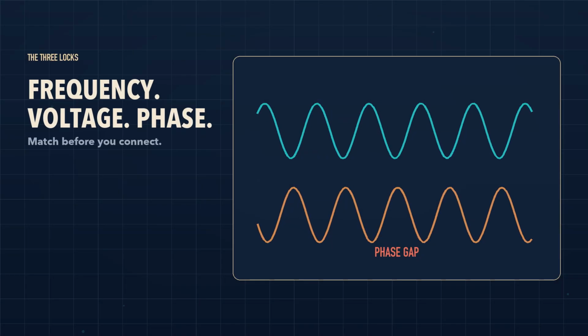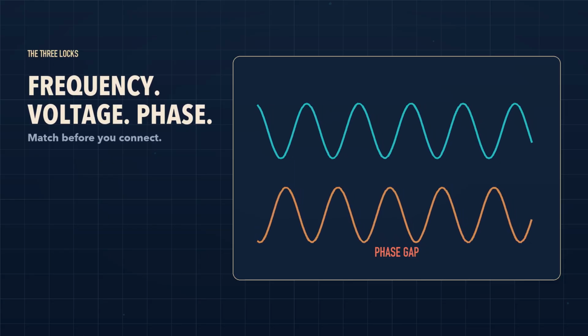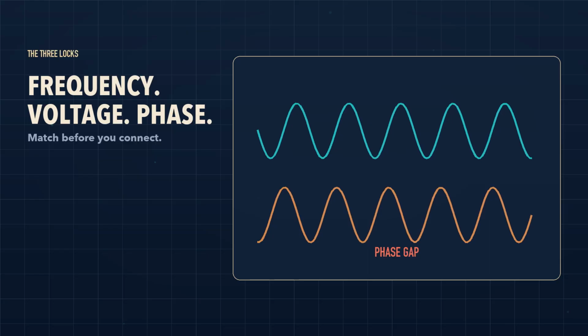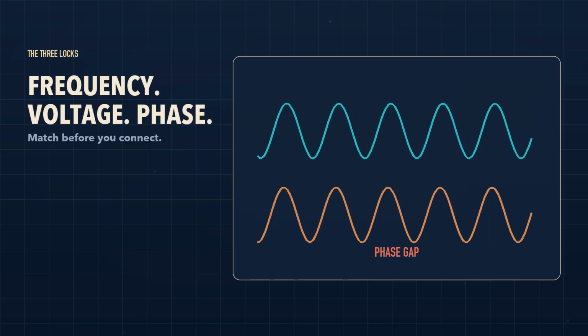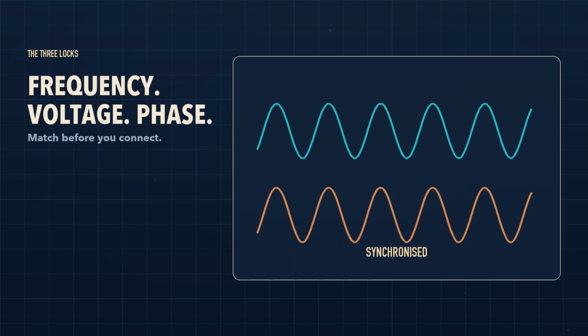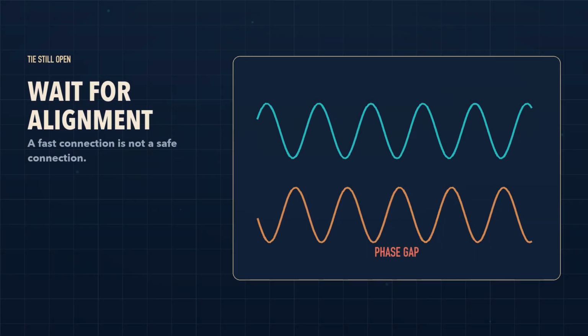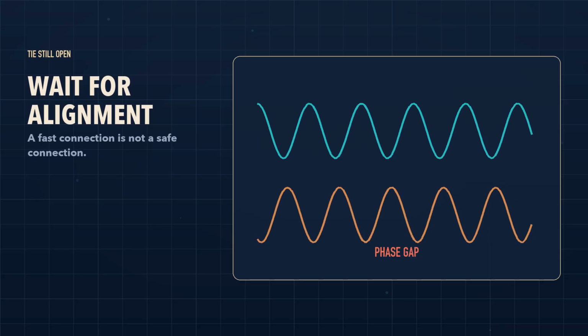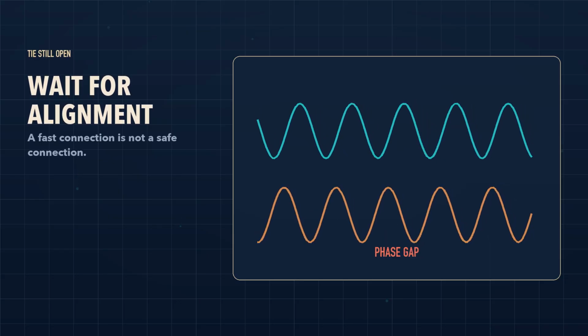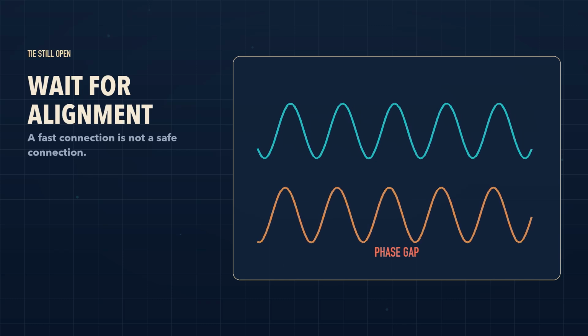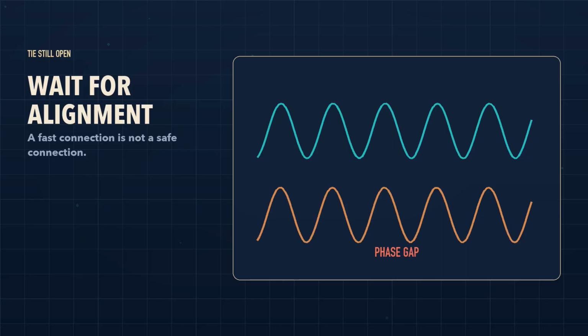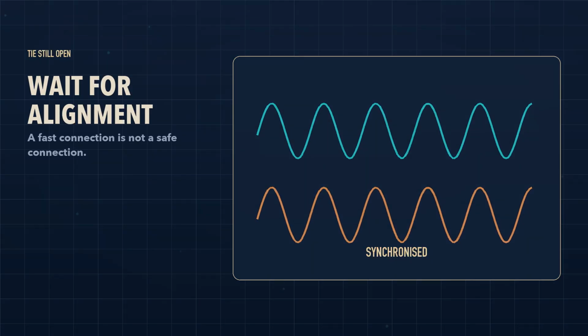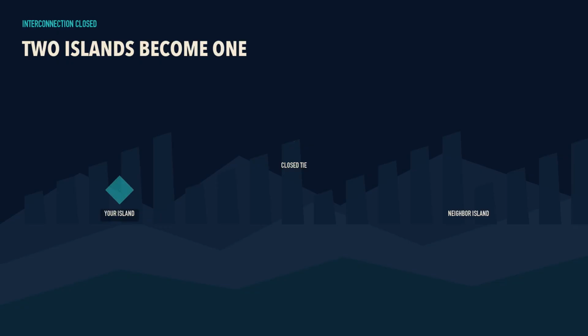The two grids cannot simply touch. Operators must align three things: frequency, voltage, and phase angle, the exact position of their alternating waves. It is a three-lock door with a very large breaker for a handle. A badly timed close can trigger violent electrical forces, protection trips, or instability. So both sides adjust generation and voltage while dispatchers watch the phase gap shrink. The breaker stays open until every lock agrees. Frequency matches, voltage matches, the waves slide into phase. Coordination approval arrives. The tie breaker closes and two fragile islands become one stronger grid.